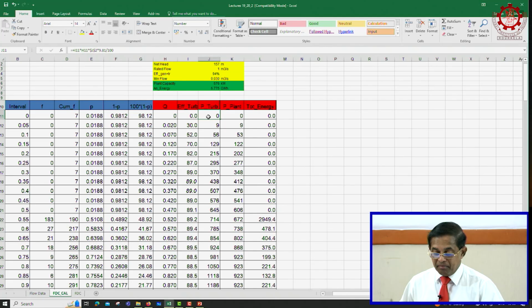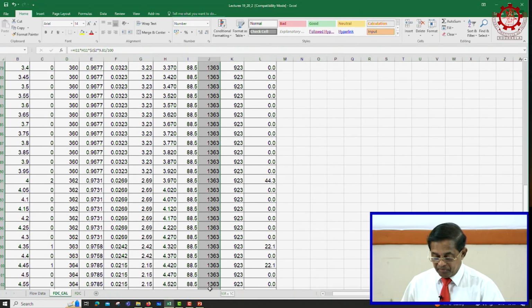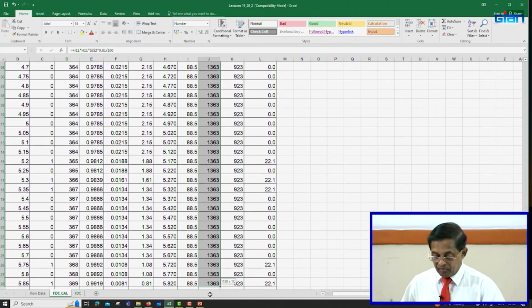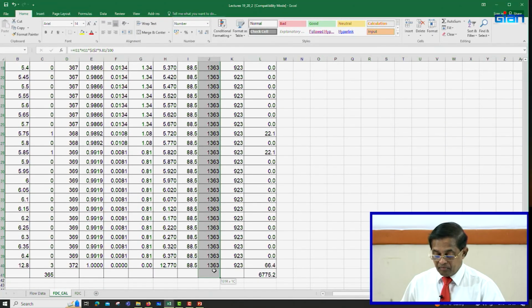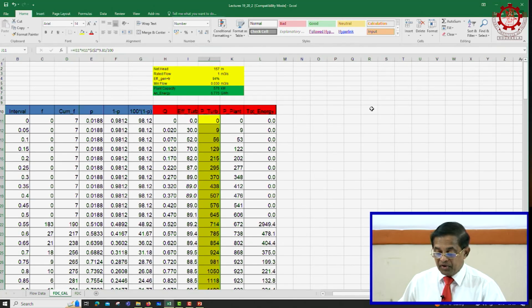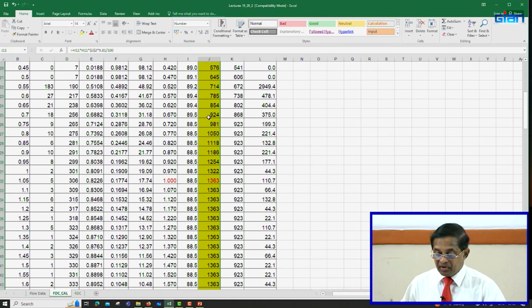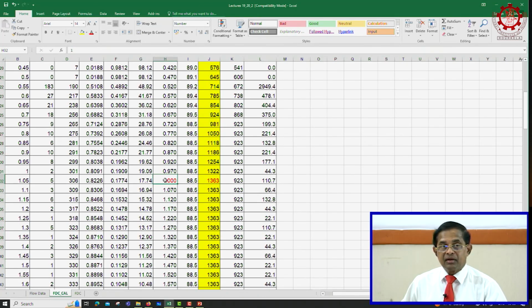So, this is the turbine capacity column, this yellow column, P turbine capacity, right. So, it increases as the flow rate increases, capacity increases 1050, 1118, 1186, 1254, 1322 and 1363, which is corresponding to 1 cubic meters per second flow rate. And when it comes to 1.070, our plant cannot use the extra water, right. The extra 0.070 of water it cannot use, because it has a capacity limit, penstock and everything.